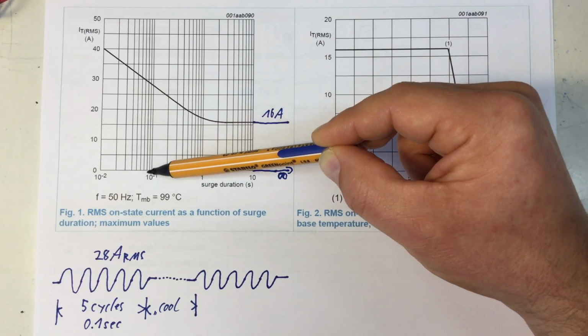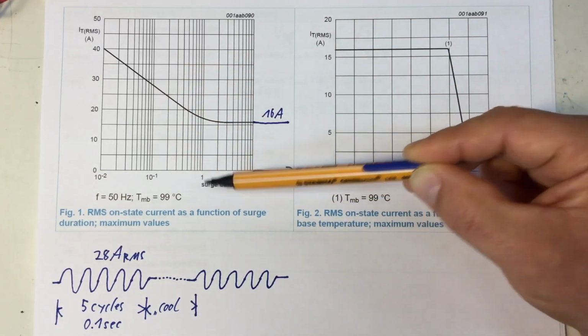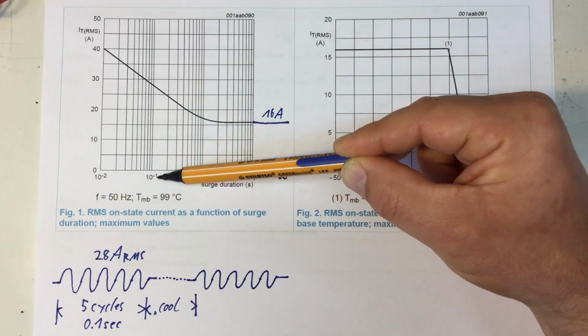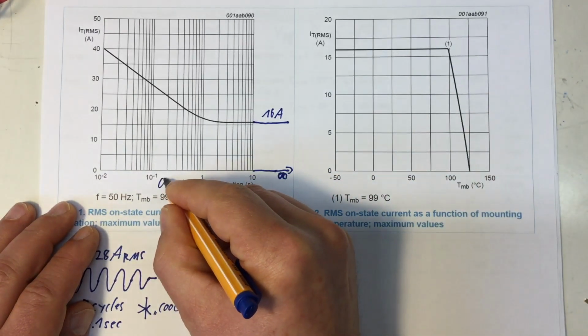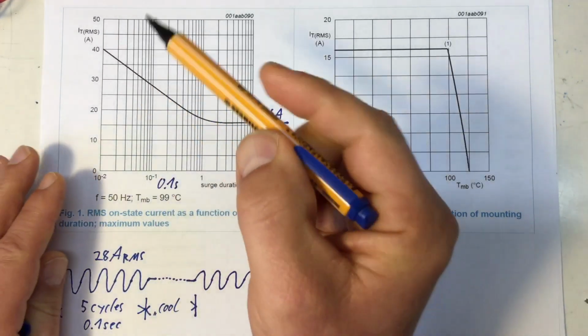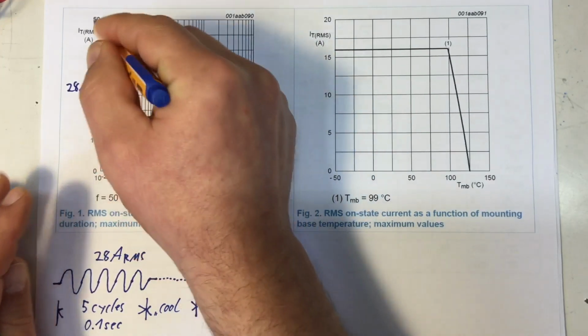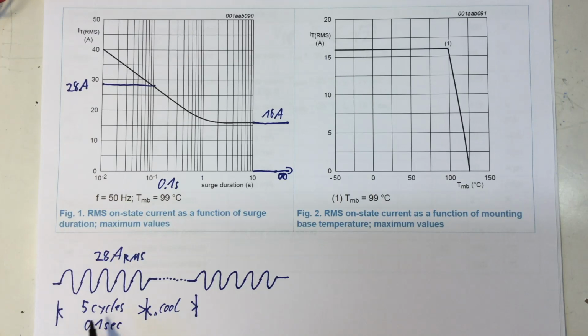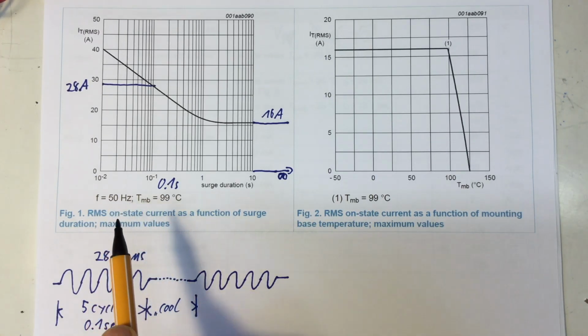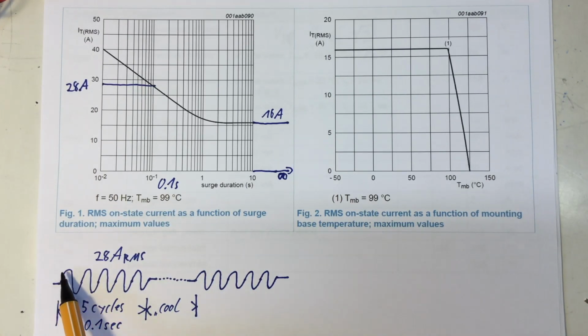However, with a shorter surge duration of 10 to the power of minus 1 seconds, so 0.1 seconds, you can pass much more current through it. Let's say that's 28 amps RMS. That means you can run the thing for 5 cycles, at 50 Hertz, 50 cycles per second, in 0.1 seconds. You can run it for a full 5 cycles at 28 amps RMS, then put in a cool down period much longer than the 0.1 seconds, and then do it again, passing 28 amps RMS through it for another 0.1 seconds.